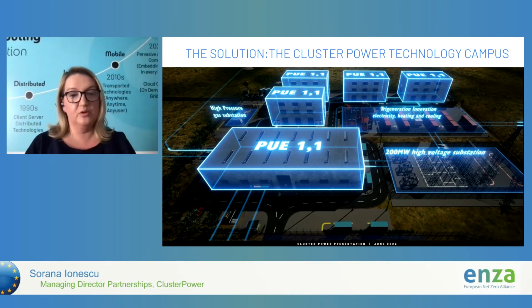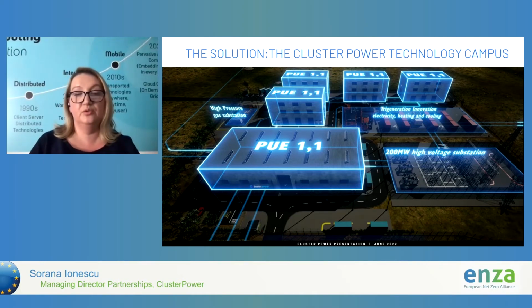The result of this innovative solution is a power usage effectiveness of 1.1, whereas the industry average globally is around 1.6 to 1.7. That means for every kilowatt of IT equipment power, for cooling and other consumption, you typically need around 0.6 to 0.7 additional kilowatts - we only need 0.1 using this solution. So efficiency was always at the core of our business and this project, and implementing this solution has helped us achieve that.